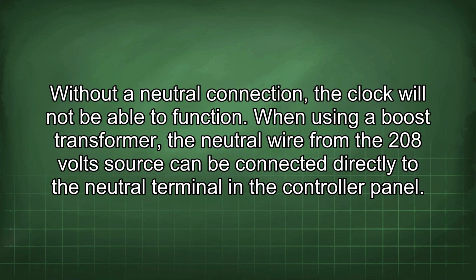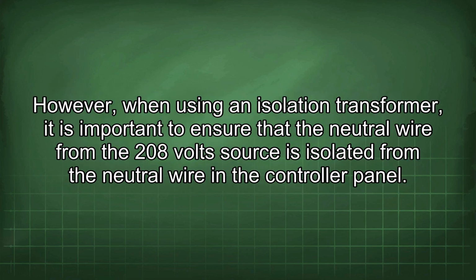Without a neutral connection, the clock will not be able to function. When using a boost transformer, the neutral wire from the 208-volt source can be connected directly to the neutral terminal in the controller panel. However, when using an isolation transformer, it is important to ensure that the neutral wire from the 208-volt source is isolated from the neutral wire in the controller panel.